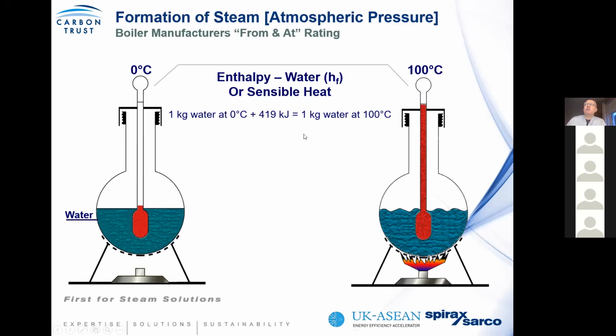However, when we start looking at the energy content of it, the specific heat capacity of water is 4.186, or 4.19 kilojoules per kg. So we need to add 419 kilojoules of energy to raise water from 0 degrees to 100 degrees. At this point, it is purely a sensible process. We're just effectively heating water towards boiling temperature at atmospheric pressure.